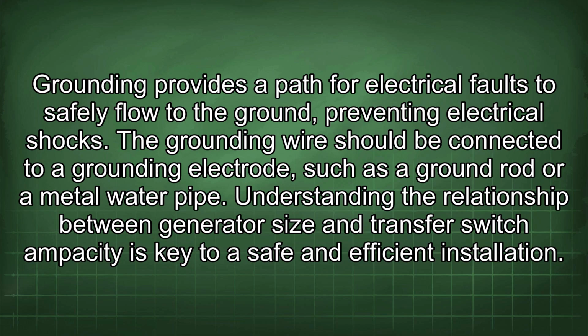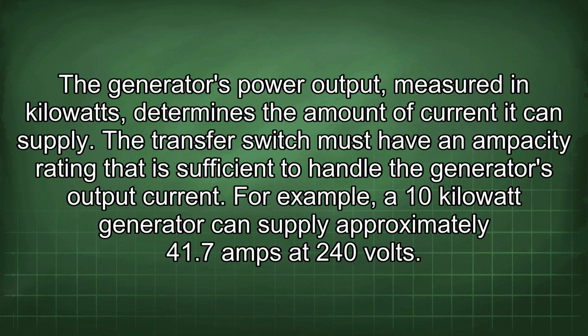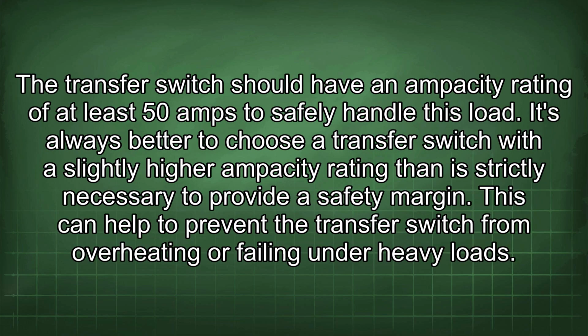Understanding the relationship between generator size and transfer switch ampacity is key to a safe and efficient installation. The generator's power output, measured in kilowatts, determines the amount of current it can supply. The transfer switch must have an ampacity rating that is sufficient to handle the generator's output current. For example, a 10 kilowatt generator can supply approximately 41.7 amps at 240 volts. The transfer switch should have an ampacity rating of at least 50 amps to safely handle this load.